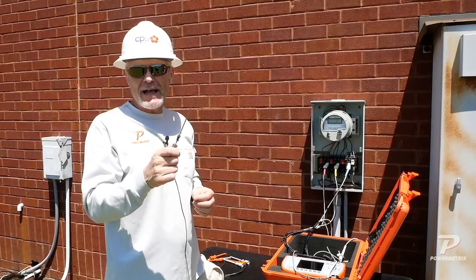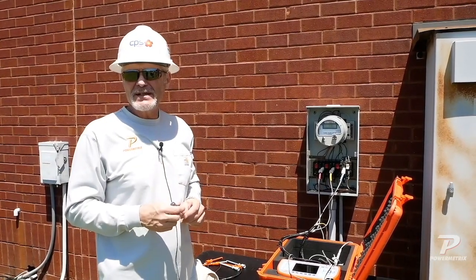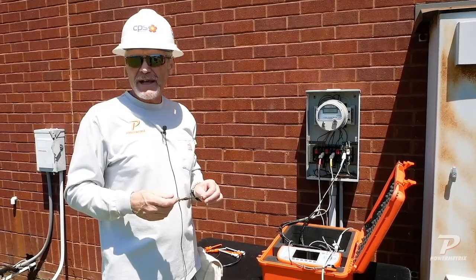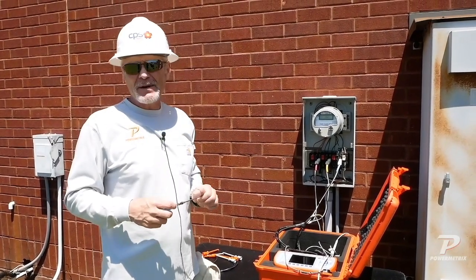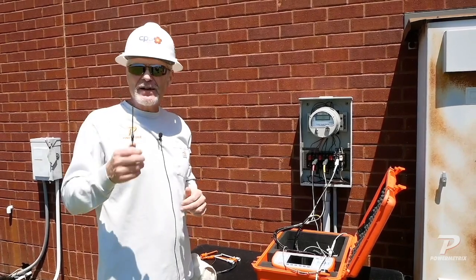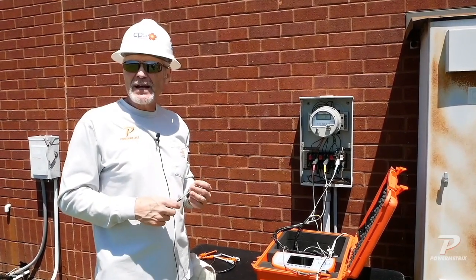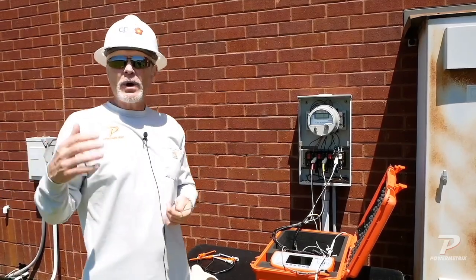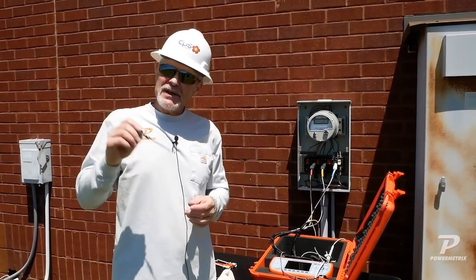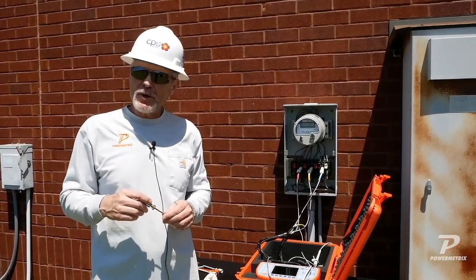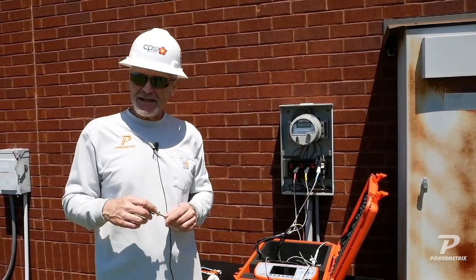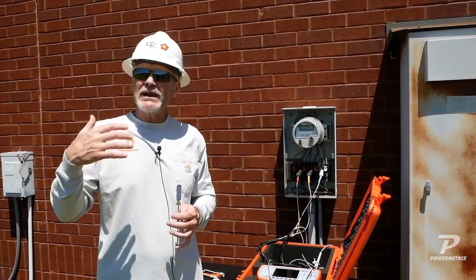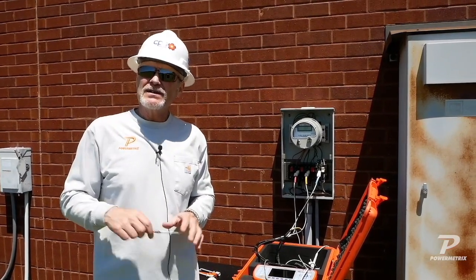So now we do not have to deal with the CT inside that transformer, because that's a much bigger issue and a bigger solution, right? This was just trying to eliminate the corrosion problems, and once we did that, it tested in fine. So if you're in one of those environments, if you're down coast, or you've got a mill right there that's emitting a lot of stuff, or there's a lot of pollution in the area, think about your connections. Corrosion is resistance, and that resistance is burden, and it's adding burden. When you get ready to test those CTs, it can cause you a problem, okay? So think about that when you're out there.